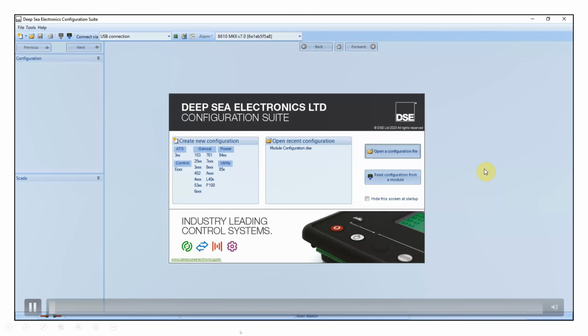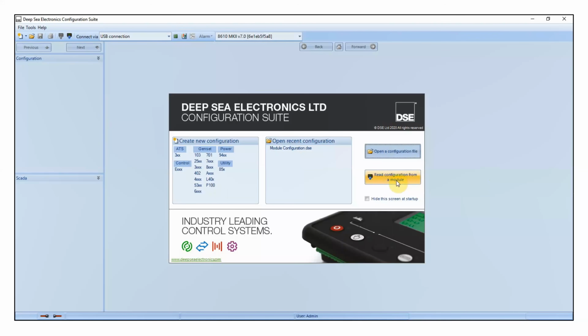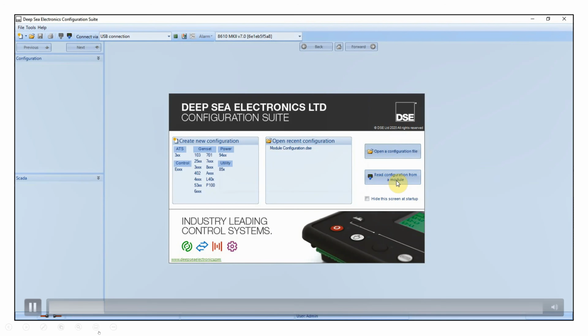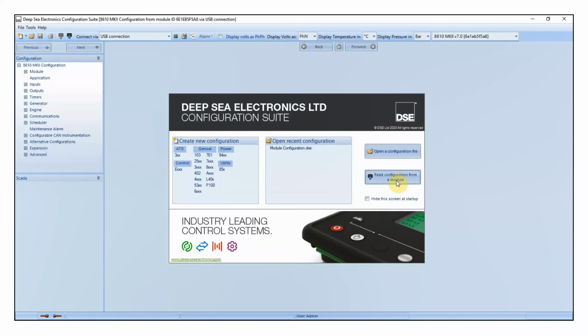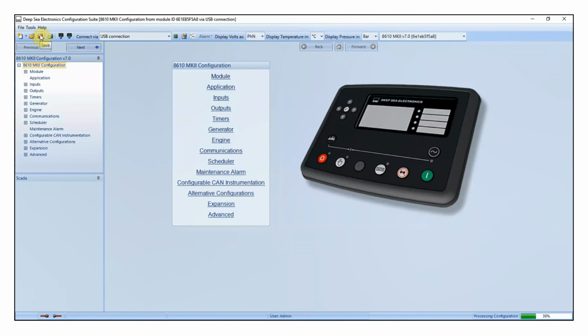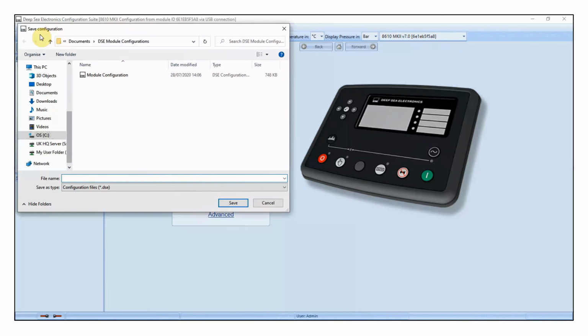The first thing we always advise you do when connecting to any DSE module is read the module's configuration. If you make any mistakes or problems whilst doing this procedure or anything with a DSE module, reading and saving will give you the option to revert back if something has gone wrong. So all I'm going to be doing first is reading the module's configuration and, once done, saving it. You can save by going to the top left-hand corner of the software and pressing the save button. Where you save the file and what you name it doesn't matter. We always advise reading and saving before you do anything else, so that if something goes wrong, you have a way of reverting back later on.